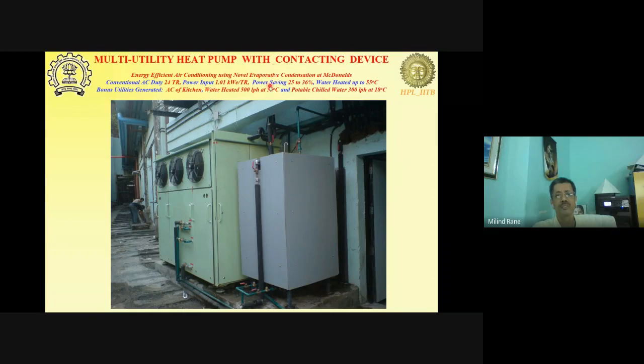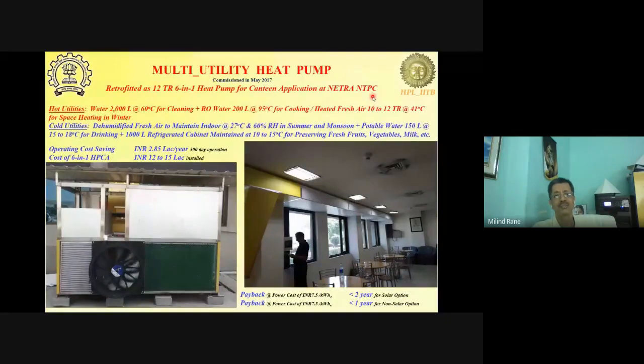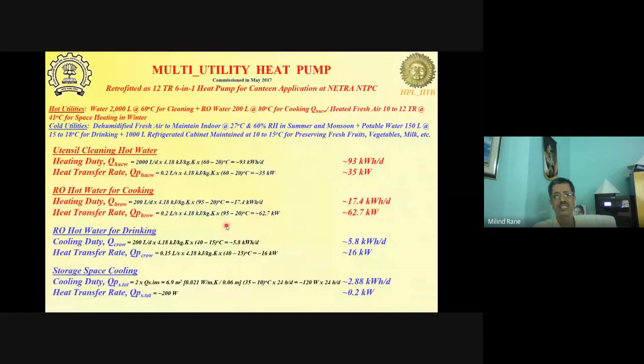It is an evaporatively condensed system at McDonald's, with 25 to 36% energy saving, and water heated to 55 degrees for sanitation. 500 liters per hour of hot water was produced as a bonus utility, and potable chilled water of 300 liters per hour at 18 degrees was also delivered. This was the multi-utility heat pump I talked about.